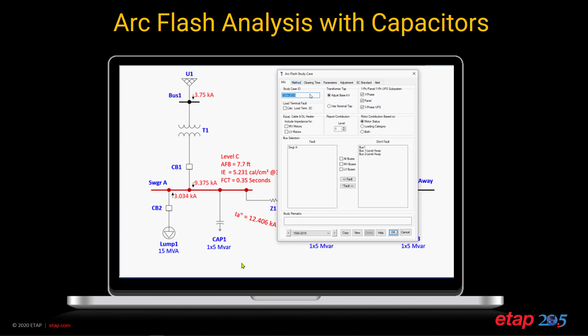ETAP can also evaluate how much incident energy is released when the system has multiple capacitor banks, and that's also illustrated in this system here by essentially compounding the energy from each of these capacitor banks to the faulted point. ETAP 20.5 therefore has been enhanced to allow you to calculate the capacitor stored energy contribution based on the new guidance provided in NFPA 70E 2021.